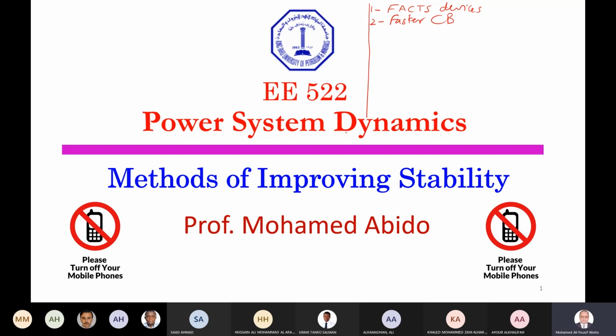And nowadays, recently, SEL company produces a circuit breaker, a relay, which depends on the traveling wave that can detect the fault in 4 milliseconds. 4 milliseconds means 1/4 of the cycle.